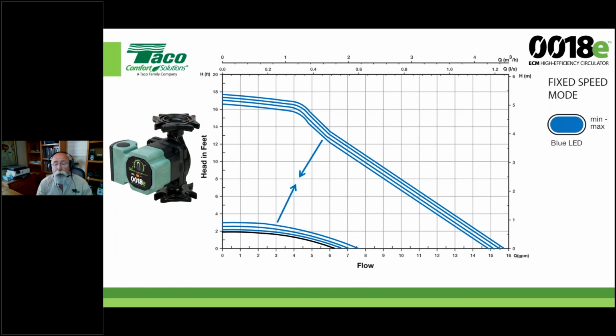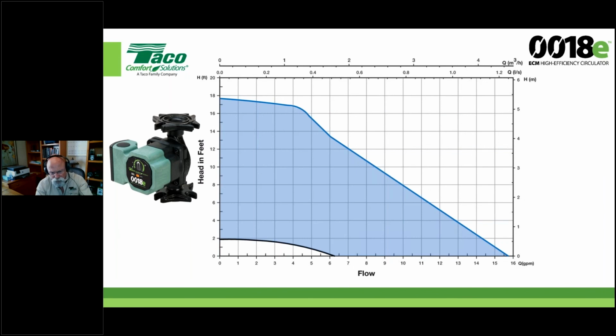But what's more important and more popular is the fact that we can put it anywhere between those two that's appropriate for that job. In this case, let's take a look at it. This is what it looks like without all those little performance curves at reduced RPMs. But let's go in. We need 10 gallons a minute. And we estimated about 5 foot of head. That's calculating a system curve, or a resistance curve, for this to be something like that. That gives me an operating point that's beautiful. I even got room to go up, but more importantly, I got room to turn this thing down.